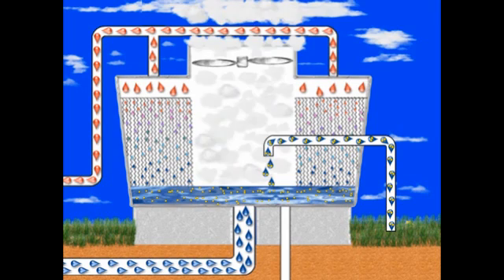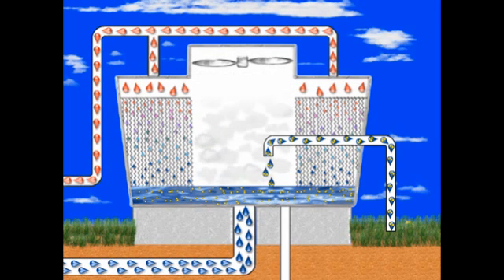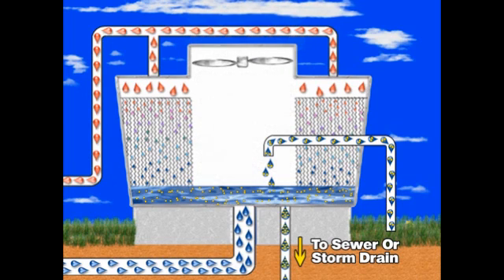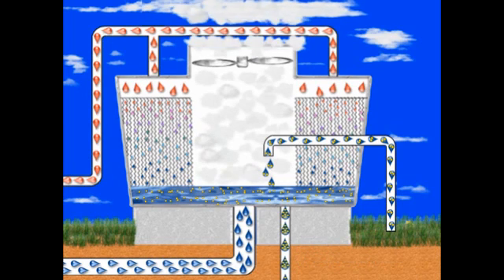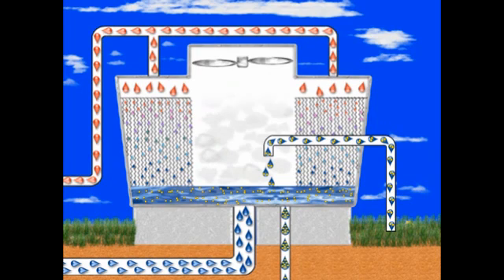To reduce the concentration of elements in the system, a bleed off valve opens and dumps a portion of the system water to drain as waste water. This waste water discharge must also be replenished by adding more fresh makeup water to the system.